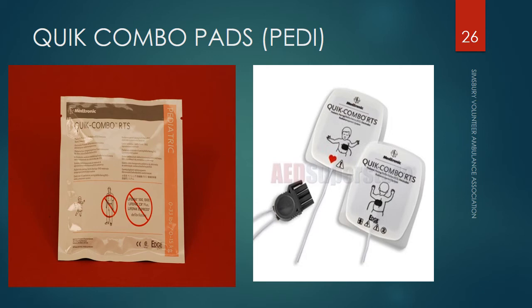Here are quick combo pads that are pedi combo pads, and pedi pads have a pediatric attenuator on them. Now, you'll notice that on the diagram or the picture on the left side of the screen, you've got a depiction of a baby in the center. So we know the pad can be used on a baby. Then you have an adult male, and you have the circle with the line through, which means we cannot use these pads on an adult patient. And then next to it, it lists the type of LIFEPAK that the pediatric pads cannot be used on. This particular set of combo pads are the combo pads that we carry on our LIFEPAK 15. We cannot use these pediatric pads on the LIFEPAK 500.